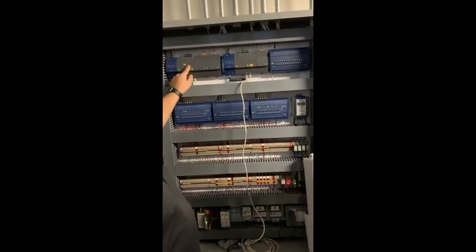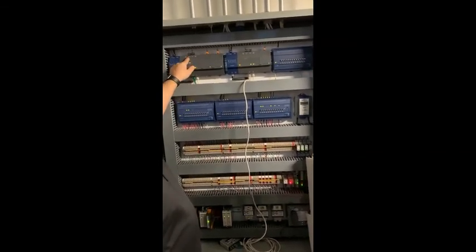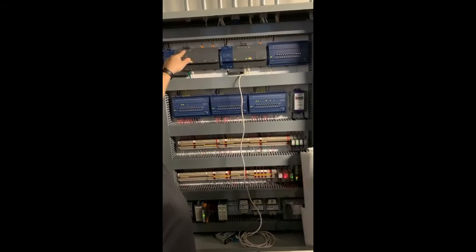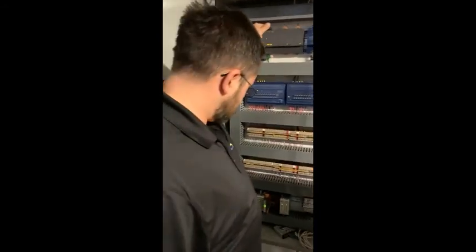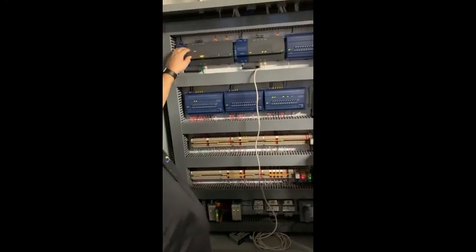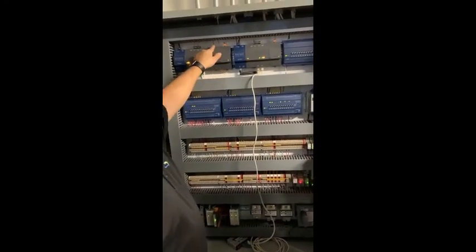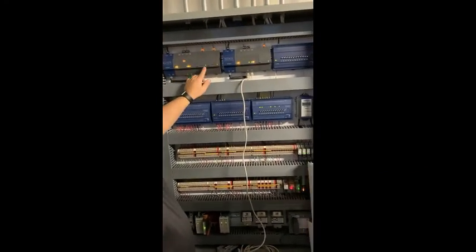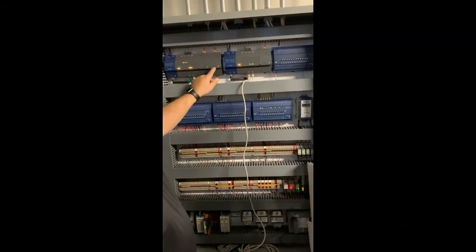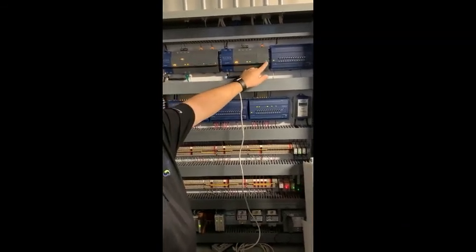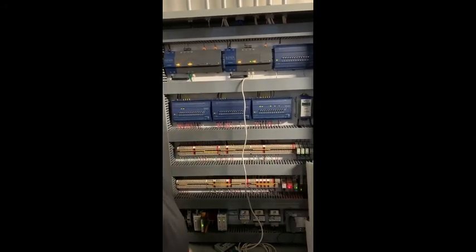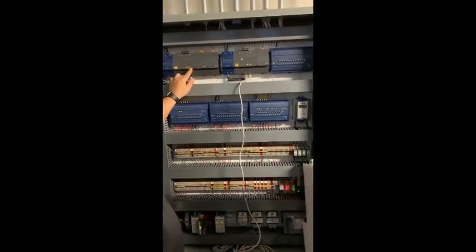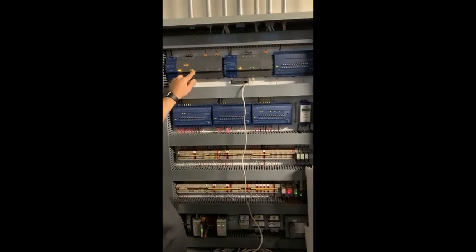We can see these are communication lights here. I think one's BACnet and one's Modbus, and then these are LON modules here, these orange type of connections. You'll see they'll communicate and blink here and there. This shows that it has power, and this is the communication status lights. And then these are the Ethernet lights, the link light and then the data transfer.